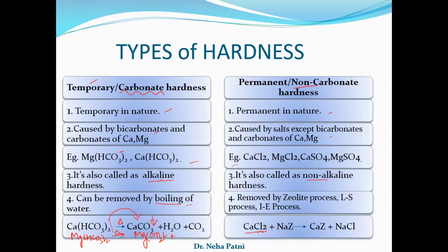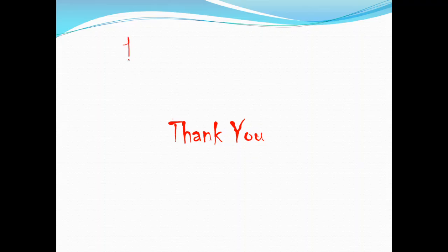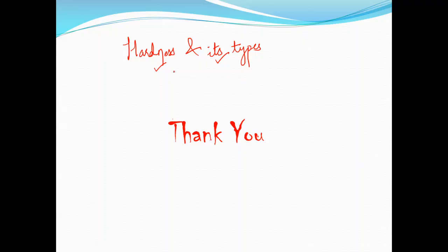For permanent hardness, the ions are quite stable and don't convert easily upon boiling. To remove permanent hardness, certain processes must be used: zeolite or permutit process, lime-soda process (where lime is calcium hydroxide and soda is sodium carbonate), and ion exchange resin process. Today we covered hardness and its types. In the next lecture I will focus on calculation of hardness.